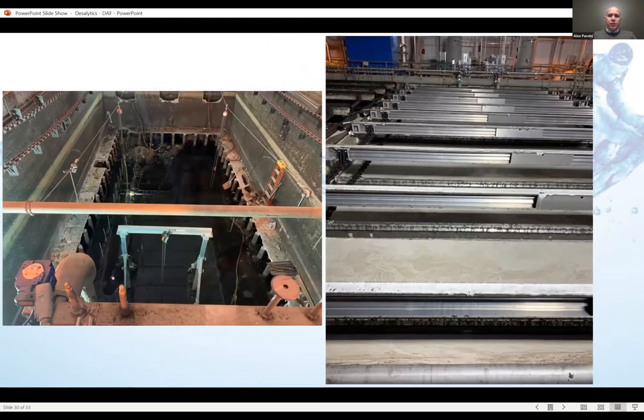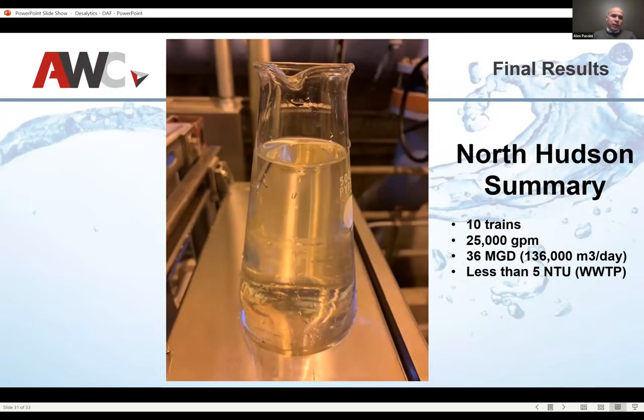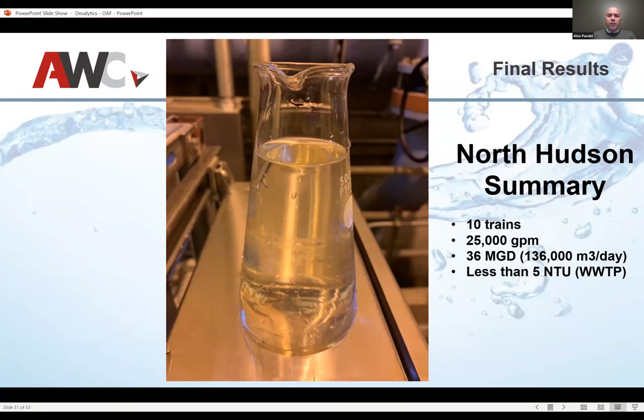That's what it looked like before and after. In just four minutes, this is a short look at how we can do retrofits. The end result: 10 trains operating at 25,000 gallons a minute, 36 MGD — 36 million gallons a day — with 136,000 cubic meters per day of water coming in at less than 5 NTU. This is wastewater, but that water quality meets the 10-state standard and allows the effluent to go back into the Hudson River.